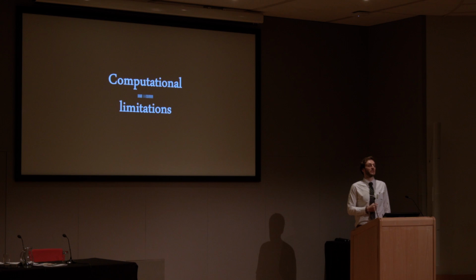And you might be looking at me and saying, you've just said that the total building system affects how fire grows and how smoke spreads, and that smoke spreading remote from the fire origin accounts for 50% of fire fatalities. Why do we curtail the domain in such a manner? It's because the computational fluid dynamics models are so computationally intensive. Millions and millions of calculations for every second of simulation time, and we might need 2,000 seconds of simulation time or something like that.